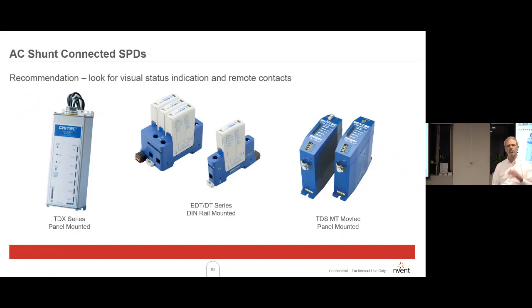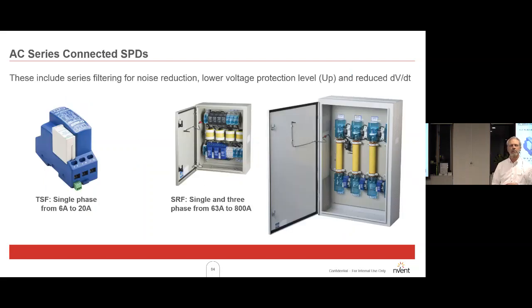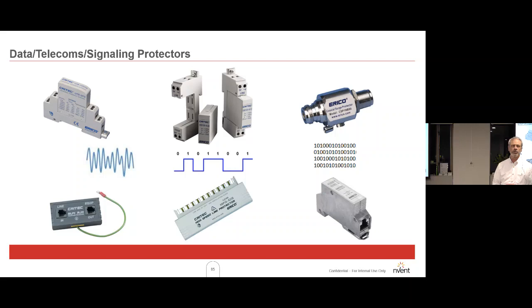And this is an example, actually it's what I've got here, just different surge diverters. Those are filters. There's a little DIN rail mounted filter on the left and larger cabinet mounted filters in the center and the right. And these are surge protection devices for things other than power. On the top left is a barrier, could be used for 4 to 20 milliamp loops or small signal applications. A DC surge diverter in the center there for 12 volts or 24 volts. Coaxial surge diverters on the right. Underneath is a phone line surge diverter, pluggable, and a Krone block surge diverter in the center. And on the bottom right is a LAN surge diverter.